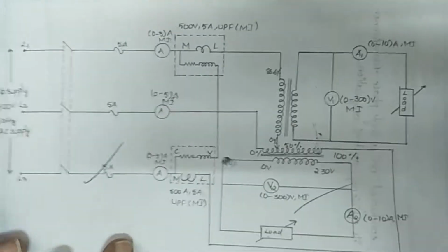400 volts, 230 volts. Clear? So now coming to the connections. Before going for connections, the nameplate details. From the nameplate details, you have to decide the rating of ammeters, wattmeters and voltmeters.